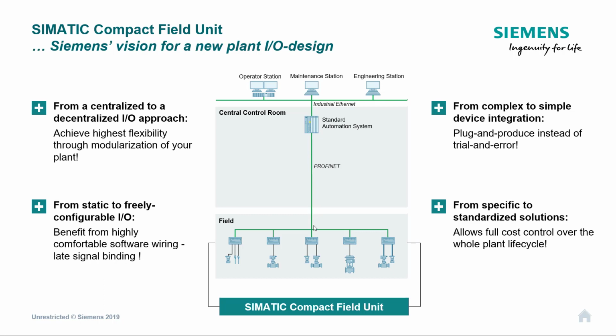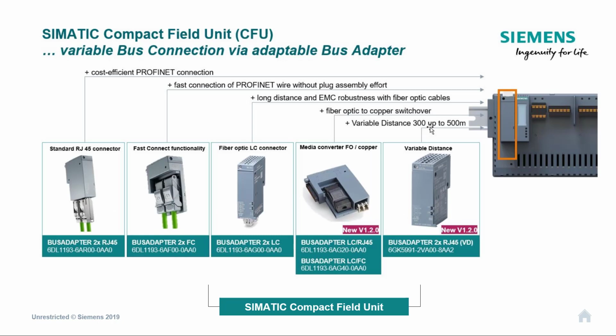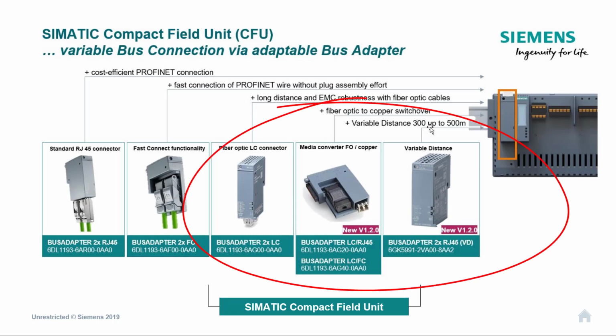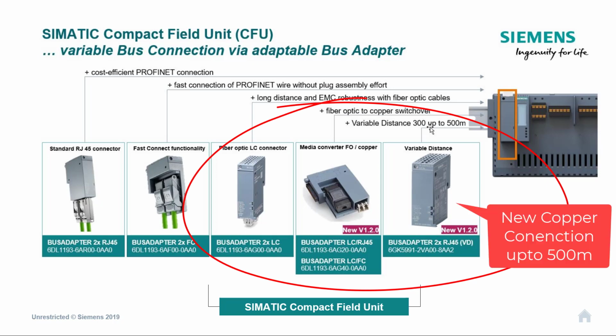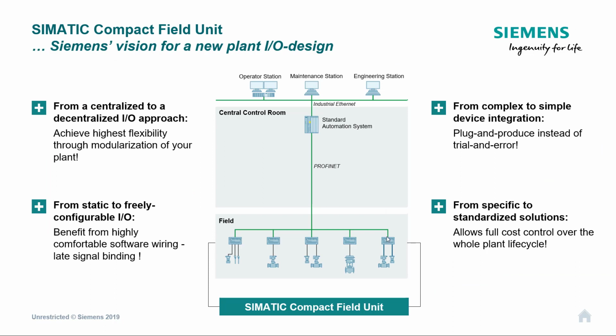The only weakness we have here is the first run of cable to the first device is 100 meters, and then to the next device is 100 meters. So in some circumstances we may have to go to fiber if the connection to our first Compact Field Unit is further away than 100 meters. But once we're in the field, as long as each one of these is within 100 meters, then we can keep adding to it within the limitations of Ethernet wiring.